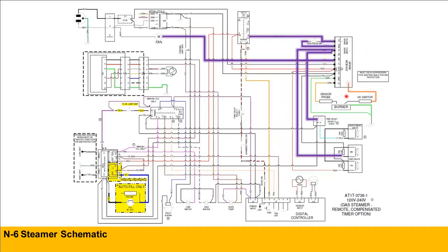All right, so if there's a lockout, that could be due to a couple of things. It could be for some reason your main valve's not opening. Or let's say your pilot's not opening, and so you have a defective pilot. So if there's no gas getting to the burner, it's going to go into a lockout. So that's one reason. It could be either your pilot or defective pilot or main valve, or the gas pressures could be low. For example, especially on an intermittent situation where the supply pressure is too low to support the equipment, or too much gas equipment on the line, so either no gas or not enough gas.